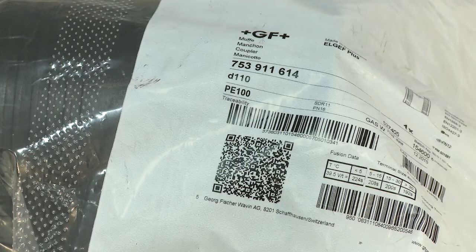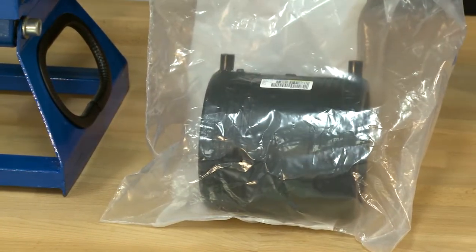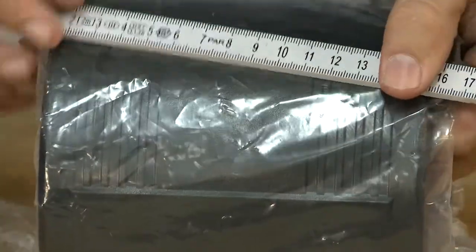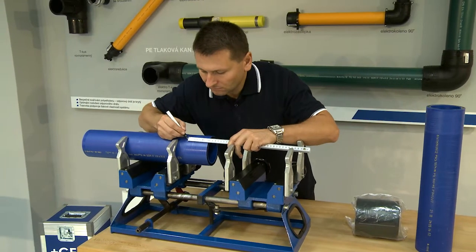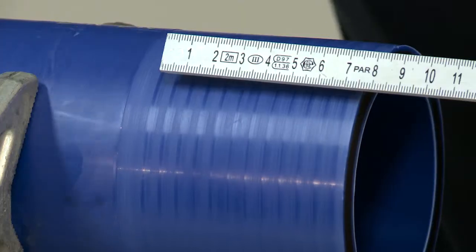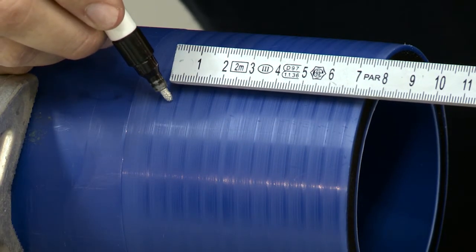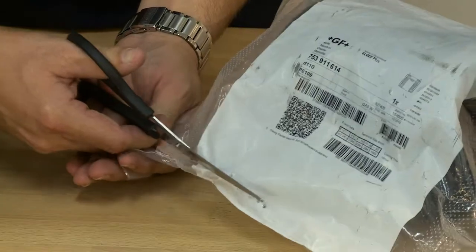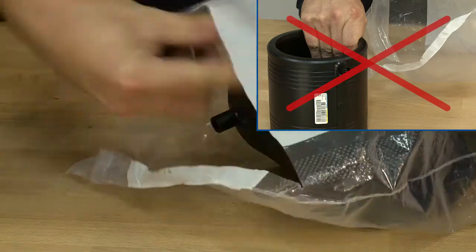Originally packed Electrofusion fittings are prefabricated in the factory to be immediately ready for welding. Re-measure the Electrofusion fitting and with three points mark an insertion depth corresponding to half the length of the Electrofusion fitting. Take the Electrofusion fitting out of its bag. Do not touch the welding zone.